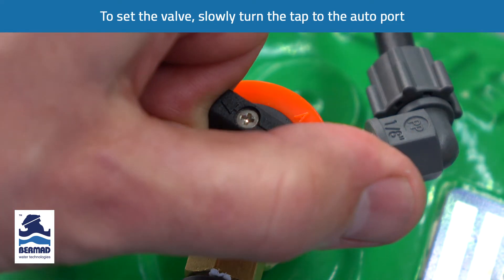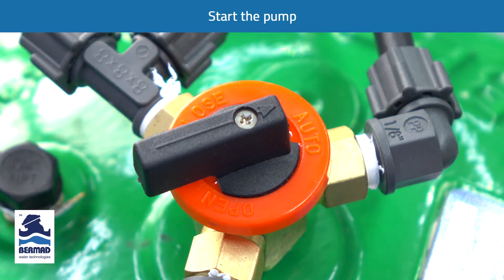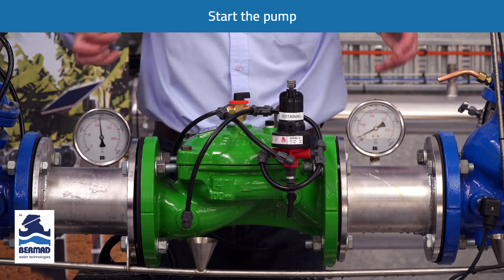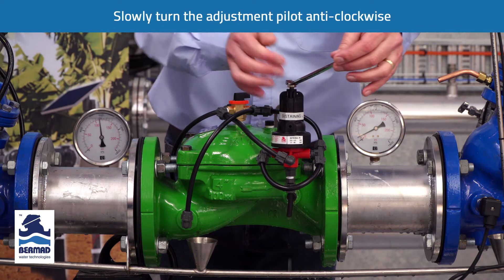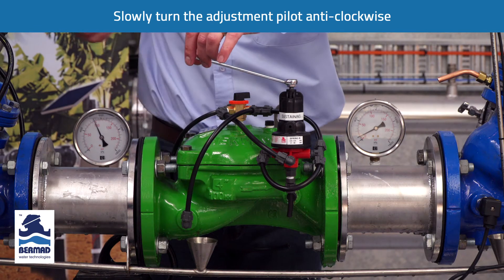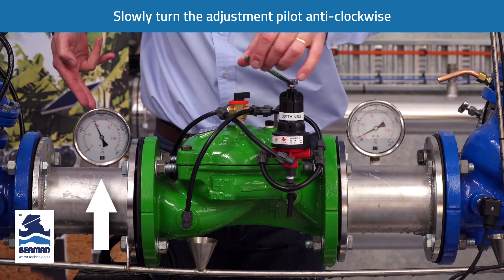We now turn the three-way tap to the auto port and we start the pump. When the pump starts, the pressure rises to a high value with next to zero on the downstream side. Slowly we turn the adjustment pilot anti-clockwise, and as we do this we see water venting out through the vent and the sustained upstream pressure starting to reduce.